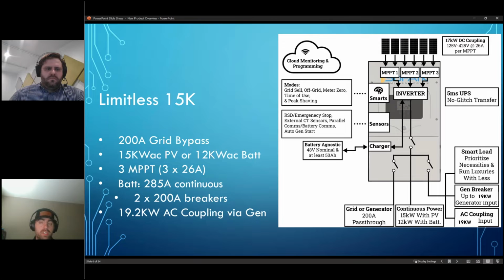We have 3 built-in MPPT charge controllers, each rated for 26 amps, so we could do up to 17 kilowatts of DC power into the MPPTs. Having 3 dedicated charge controllers is beneficial because it allows different facing arrays, each with its own dedicated charge controller, instead of mixing and matching and getting lower production performance on the same MPPT. So it's very customizable and very powerful in that sense.